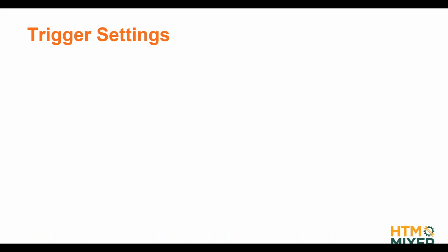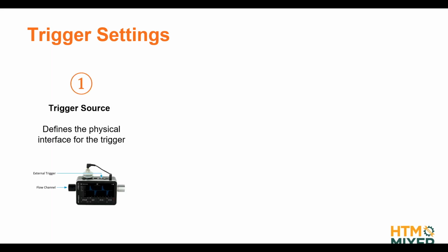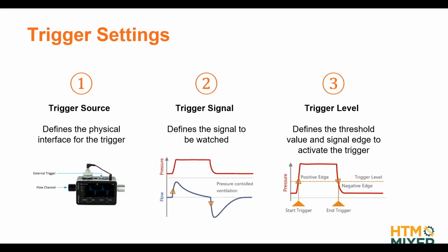Before we talk about how we can ensure that and how we can find suitable trigger settings, let's talk about what the trigger settings are, or what parameters we need to tell the device. Trigger settings actually consist of three main parameters. The first one is a trigger source, then a trigger signal, and a trigger level. The trigger source defines the physical interface for the trigger. This could, for example, be the flow channel of our gas flow analyzers, or a pressure port of our gas flow analyzer. And all gas flow analyzers out there, or at least all the ones I've seen so far, also have an external trigger interface. Some ventilators offer a digital TTL signal that they trigger whenever they trigger the breath, and you can connect that to your gas flow analyzer, and that then actually triggers your gas flow analyzer.